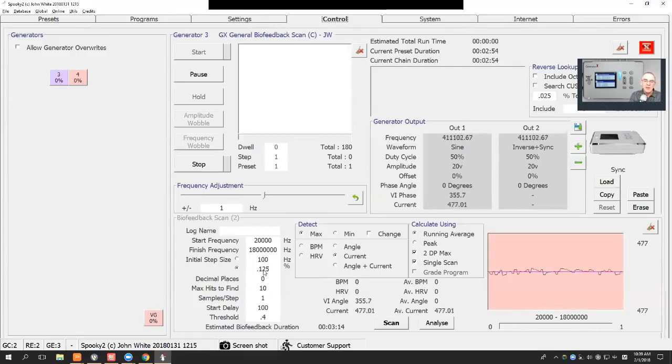There's always a delay before the body gives a response, whether it's through galvanic response, which is your skin having some perspiration on the surface, or whether it's your heartbeat. GeneratorX is not relying on the body anymore. It's just relying on the cells and the way that the cells behave electrically. And so any results, even on the very first wave cycle, are known by GeneratorX. And so the scans are much faster, and you don't need to increment with such a small value.